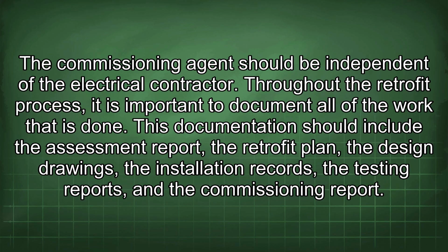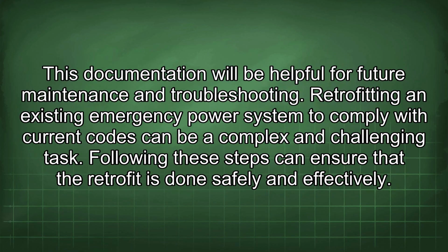Throughout the retrofit process, it is important to document all of the work that is done. This documentation should include the assessment report, the retrofit plan, the design drawings, the installation records, the testing reports, and the commissioning report. This documentation will be helpful for future maintenance and troubleshooting. Retrofitting an existing emergency power system to comply with current codes can be a complex and challenging task. Following these steps can ensure that the retrofit is done safely and effectively.